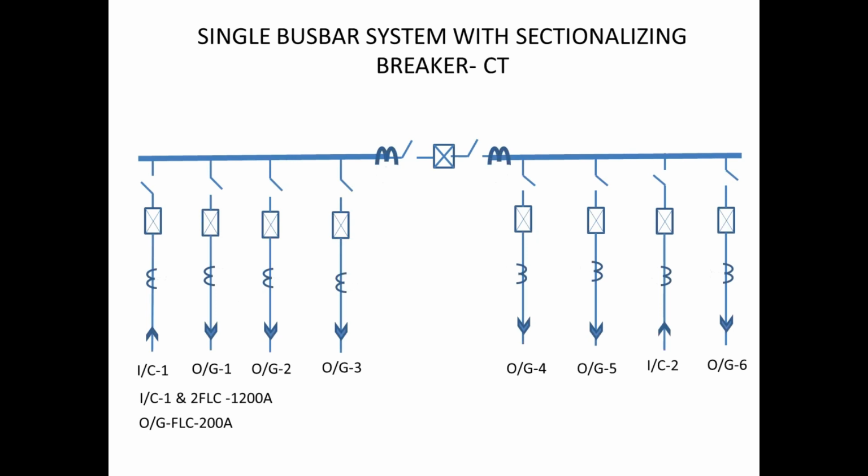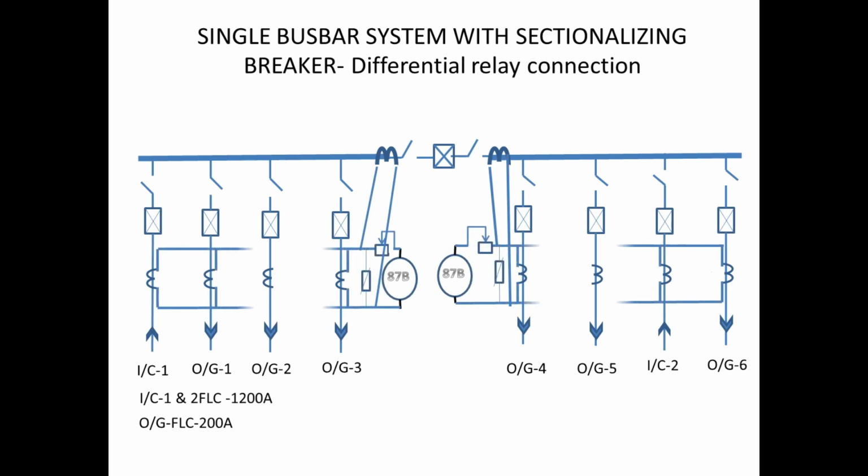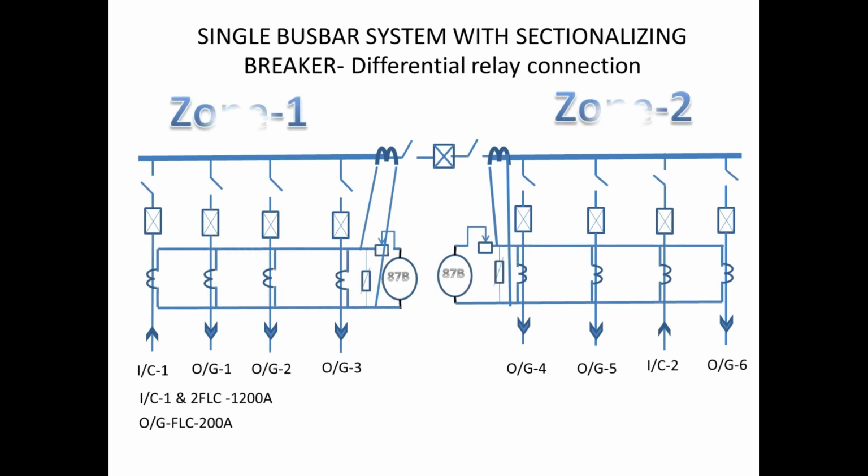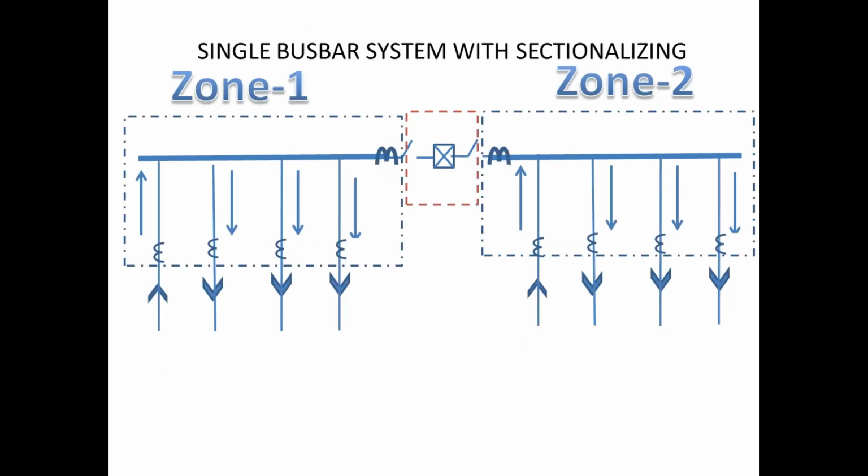According to this SLD, it has two zones. Over these two zones, the bus coupler CT selection is very important. If we include the corresponding side zone CT of a bus coupler, then it will not work properly. We will see why, and what will happen in a fault condition.